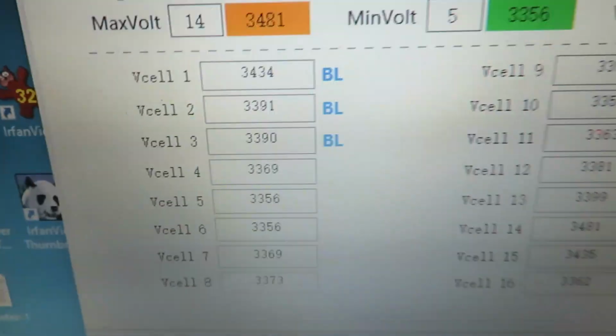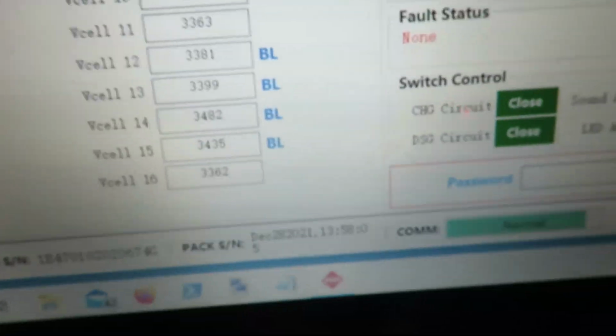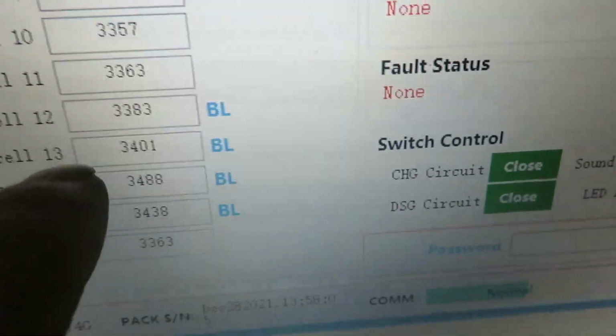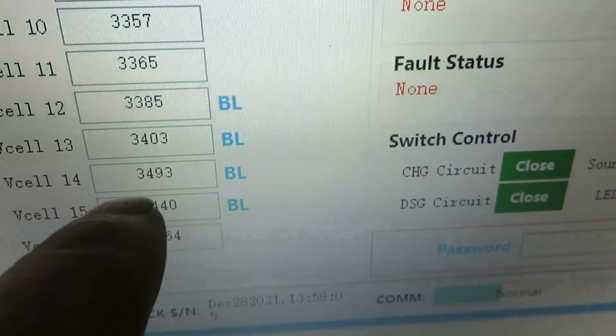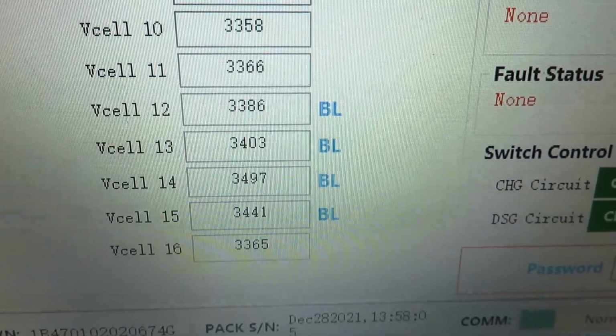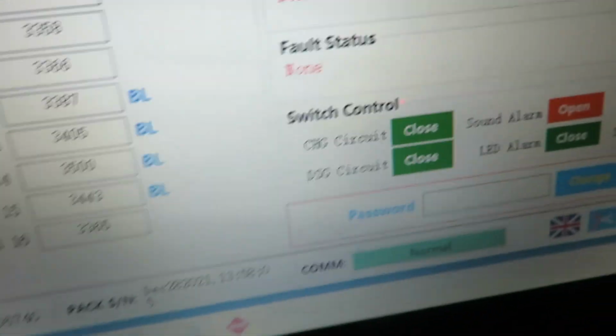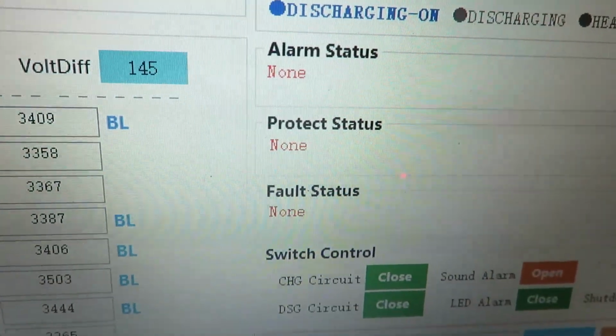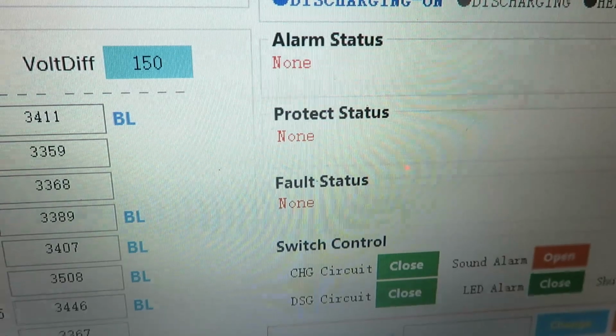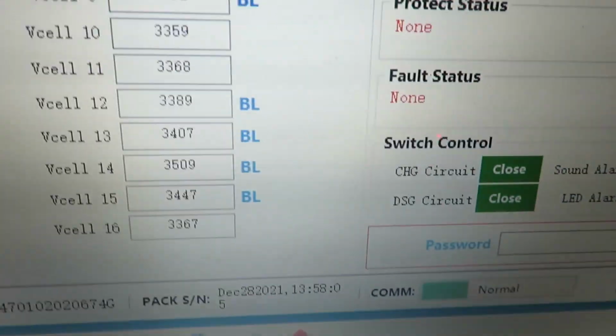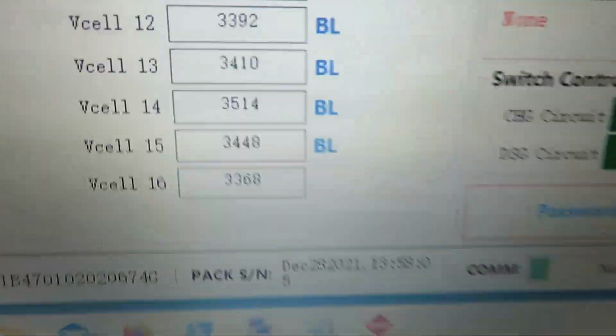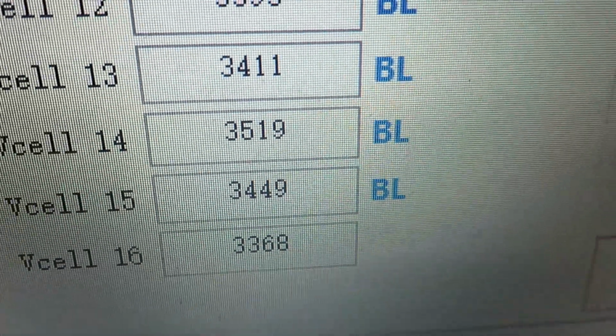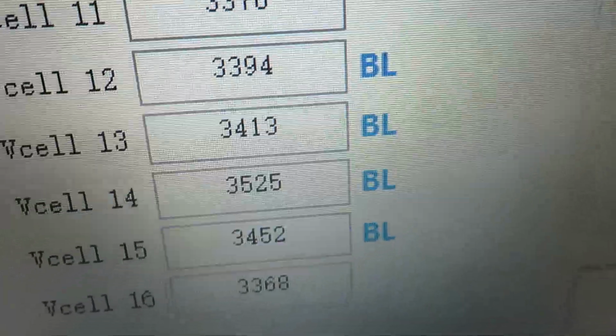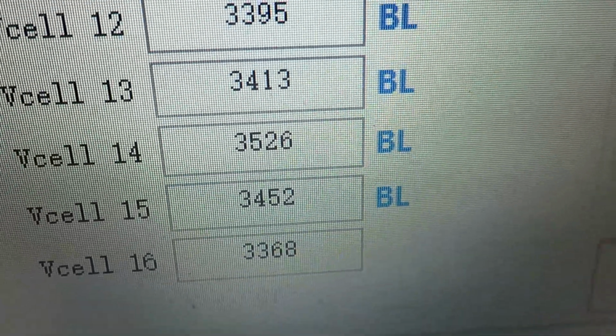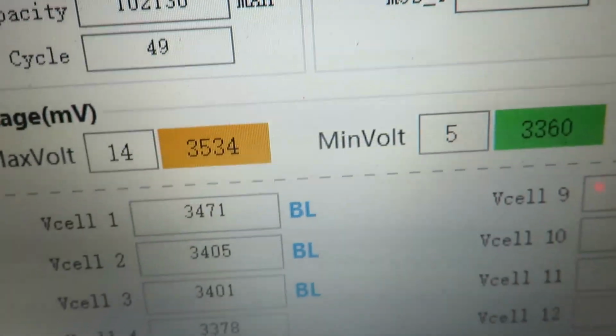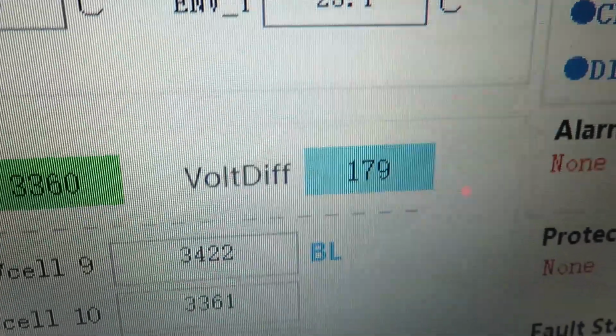So who's the high cell? 3482 right here, the one that's always high, cell 14. As soon as that gets to 3.6, I guess it'll go into overvolt protection, overvolt alarm. It's coming up pretty fast. We'll just see how long that takes. Didn't take long the last time, it's so much higher than the others. Look at the differential climb.